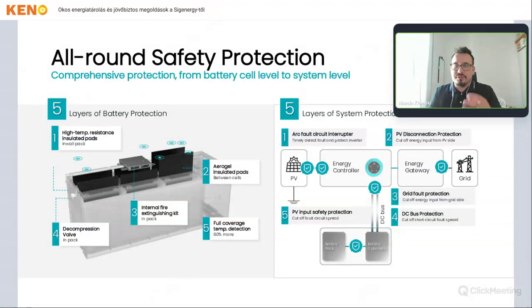There are different layers of protection in the inverter itself. I'd like to show the residual current monitoring unit, AFCI, which is generally very well known. There's additional ground DC ground bus protection - a feature I haven't found in any other manufacturer at this moment. This additionally protects our TNC type inverter, and those inverters can be easily connected to existing 400 volt installations.